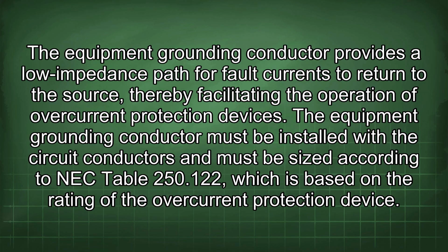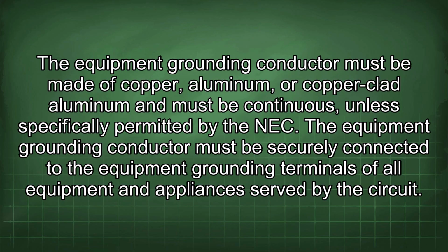The equipment grounding conductor must be installed with the circuit conductors and must be sized according to NEC Table 250.122, which is based on the rating of the overcurrent protection device. The equipment grounding conductor must be made of copper, aluminum, or copper-clad aluminum and must be continuous, unless specifically permitted by the NEC. The equipment grounding conductor must be securely connected to the equipment grounding terminals of all equipment and appliances served by the circuit.